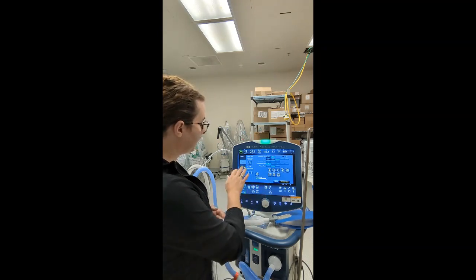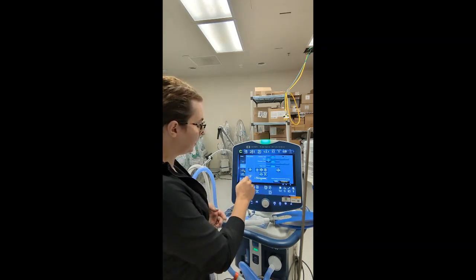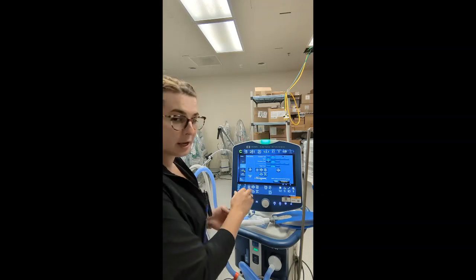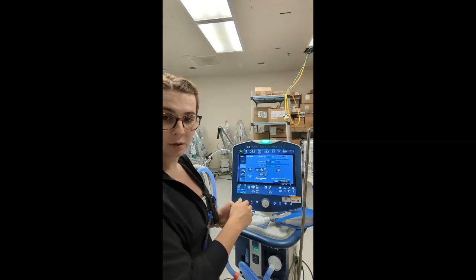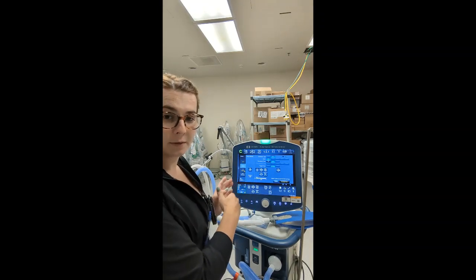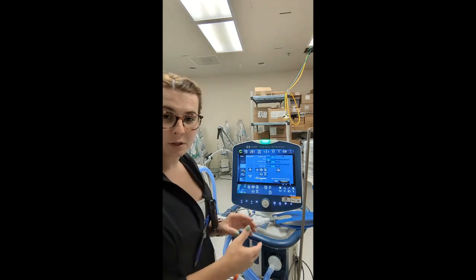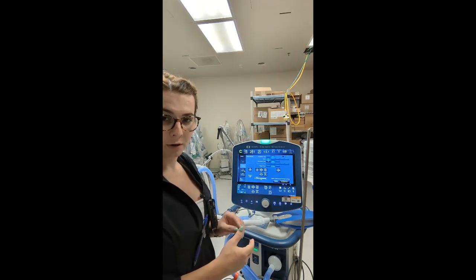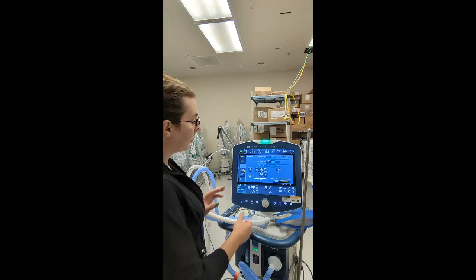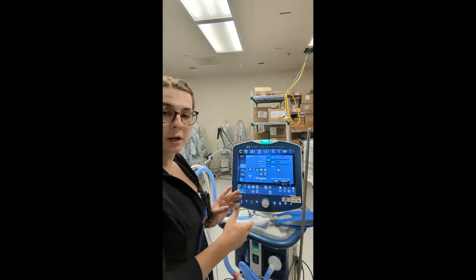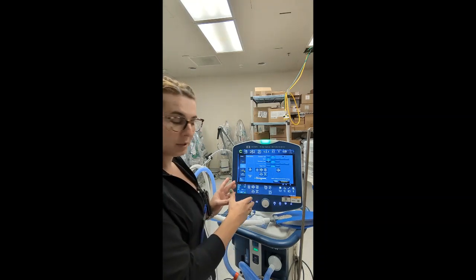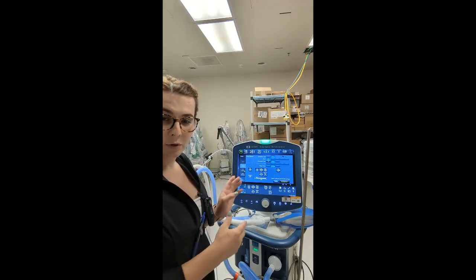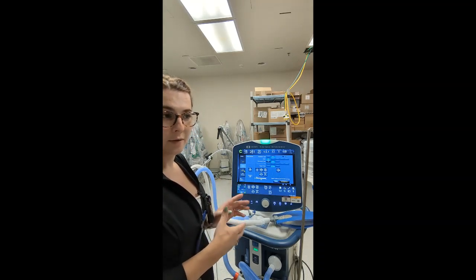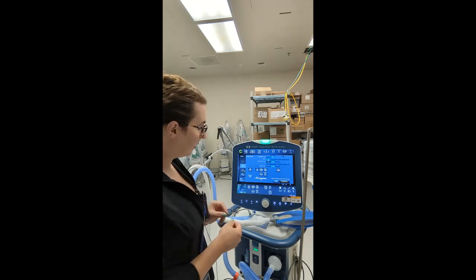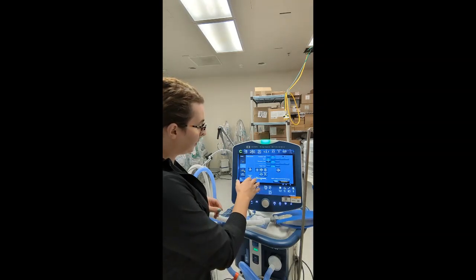Next, we're going to verify our apnea alarms. They should be the same as they were when they were invasive if you swapped them over, but it's always good practice to double check your alarm settings. This is a great thing too, because we don't need to add a backup rate since we have these apnea alarms. Unlike the V60, where having a backup rate is completely necessary. So we set our apnea alarm, and then we're going to go check our alarms.